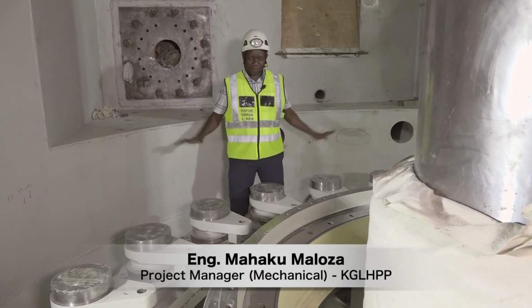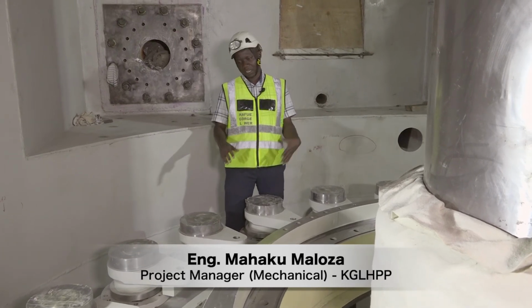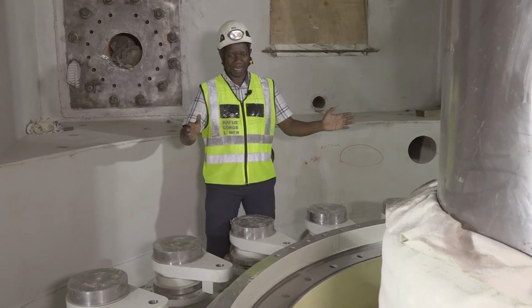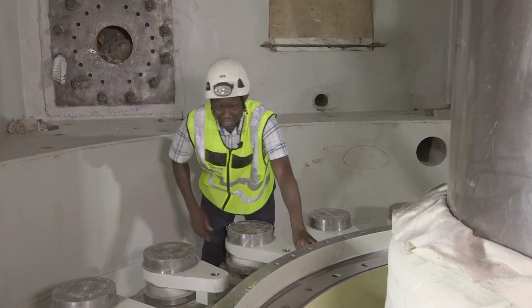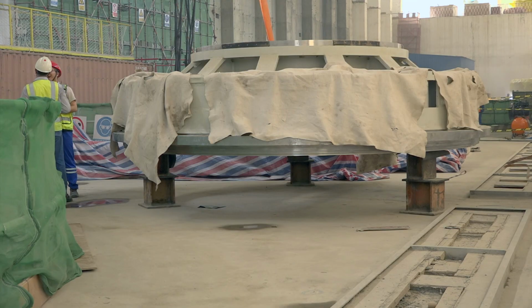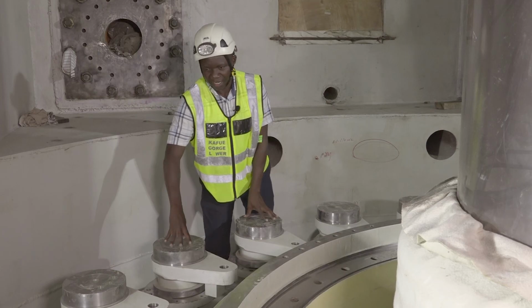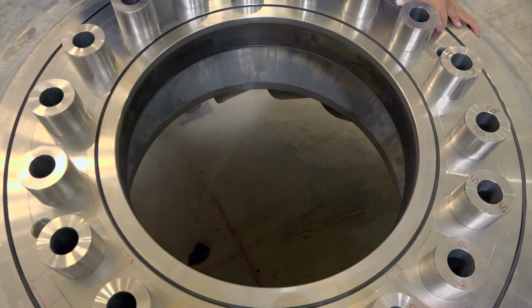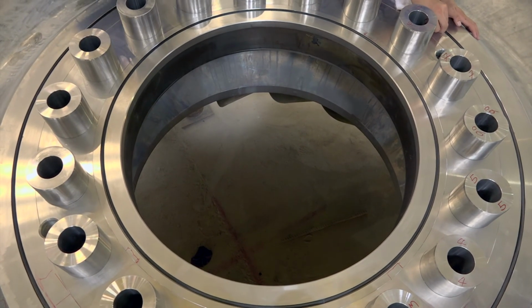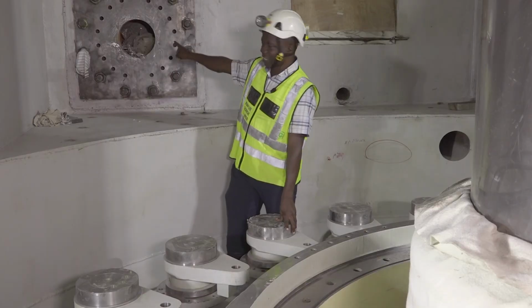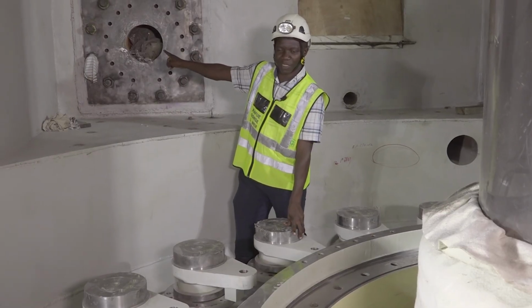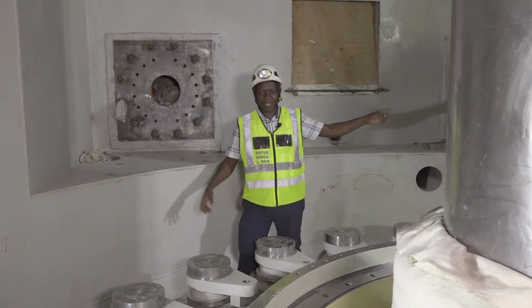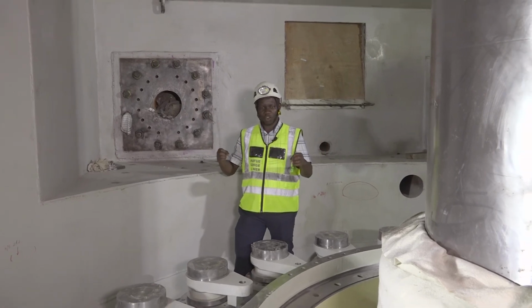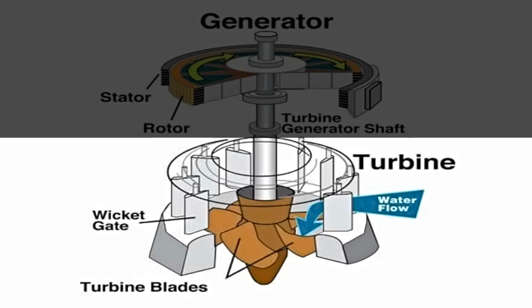So now the turbine area is all covered. We just have a few pieces coming up: a regulating ring will sit here, which regulates the opening and closing of the guide vanes. The movement of this regulating ring is provided by servo motors, one here and another here, operated by high pressure oil to open and close the guide vanes, or wicket gates.